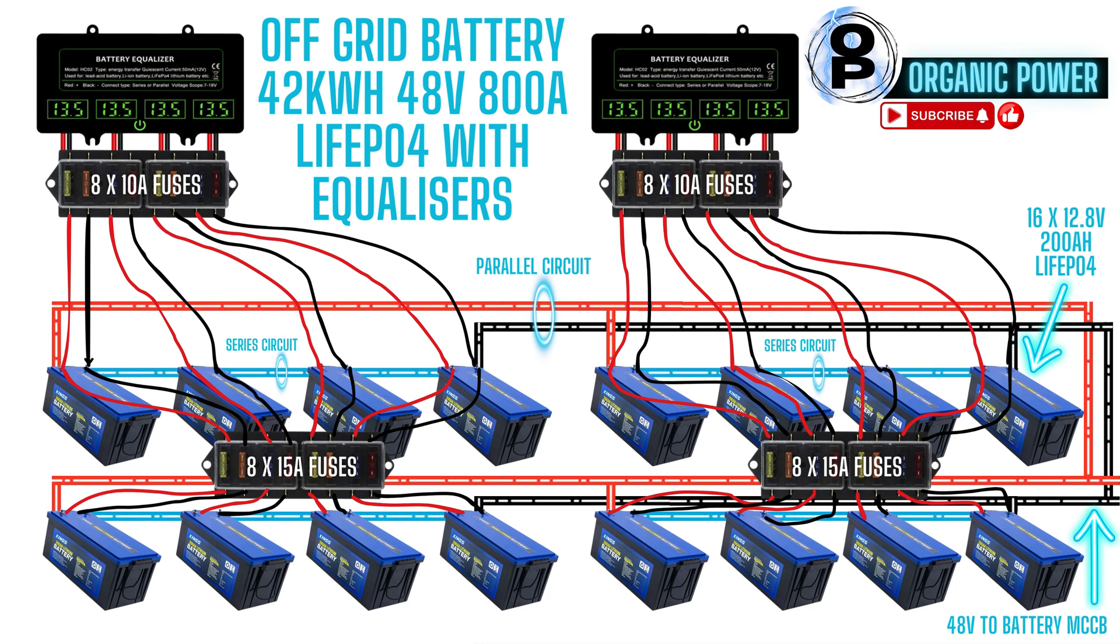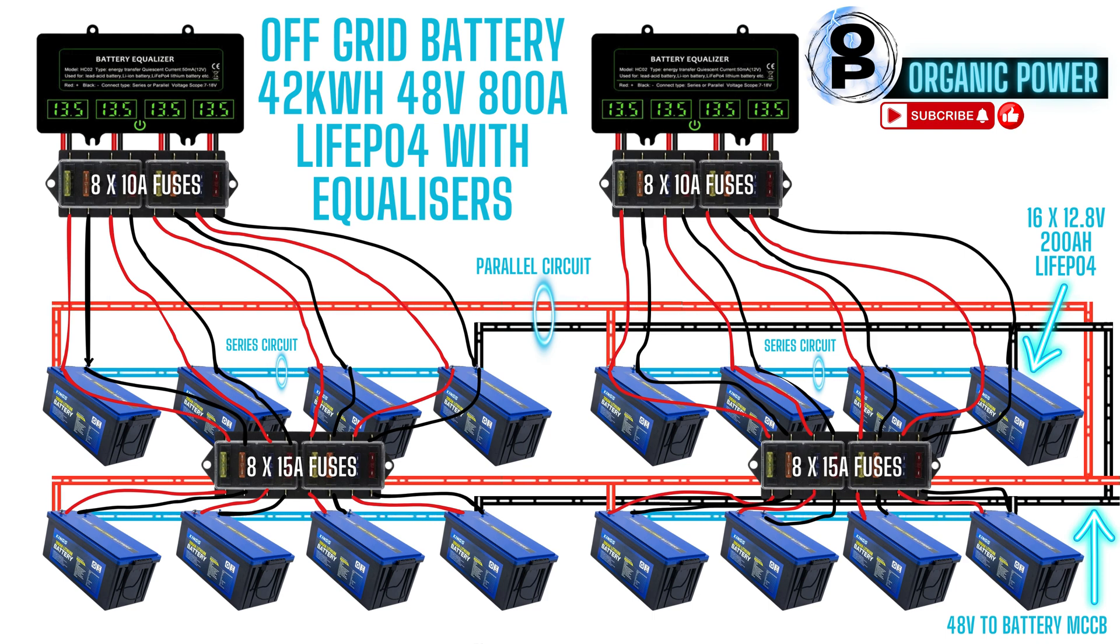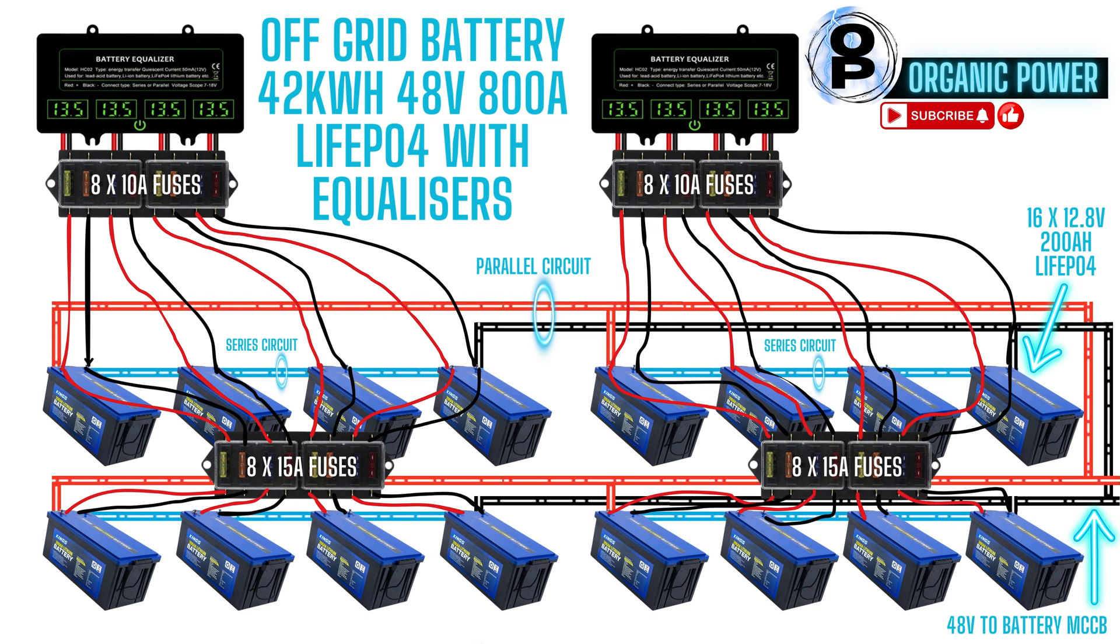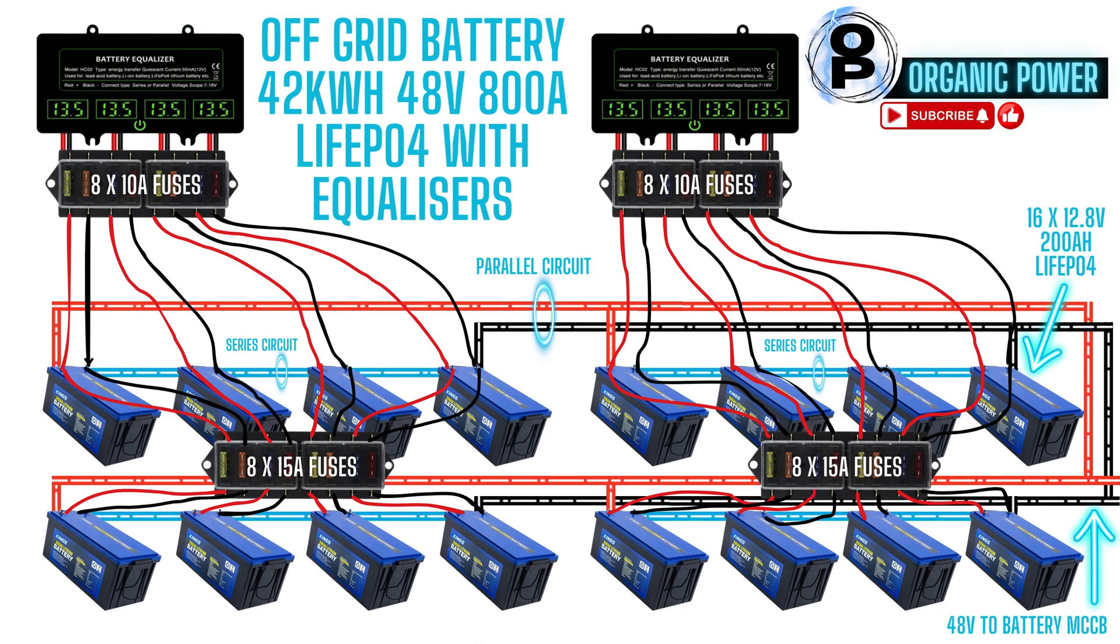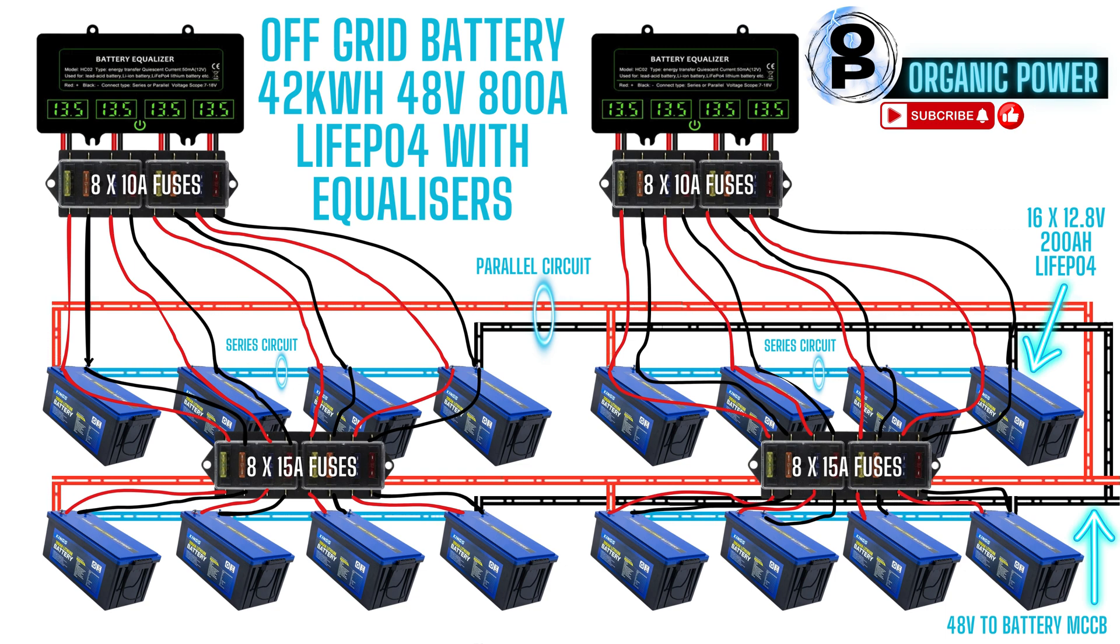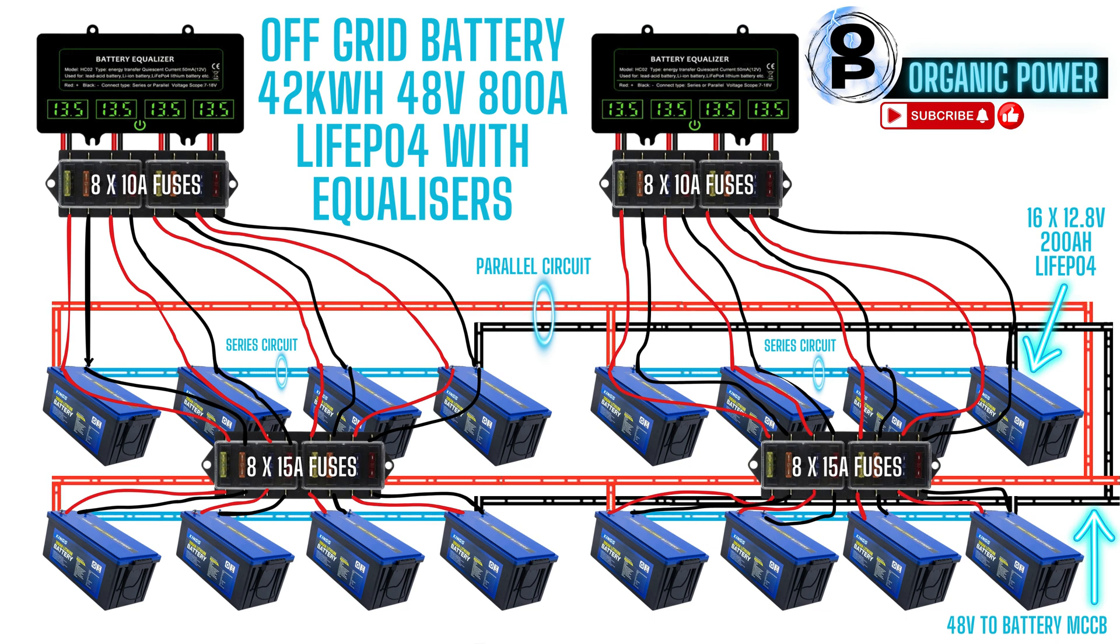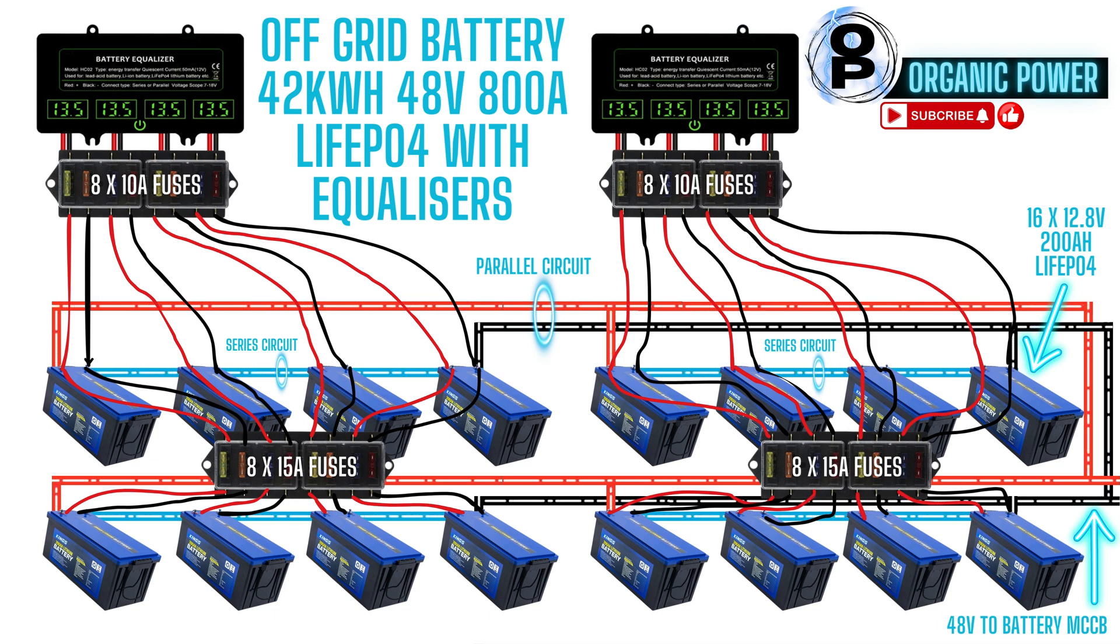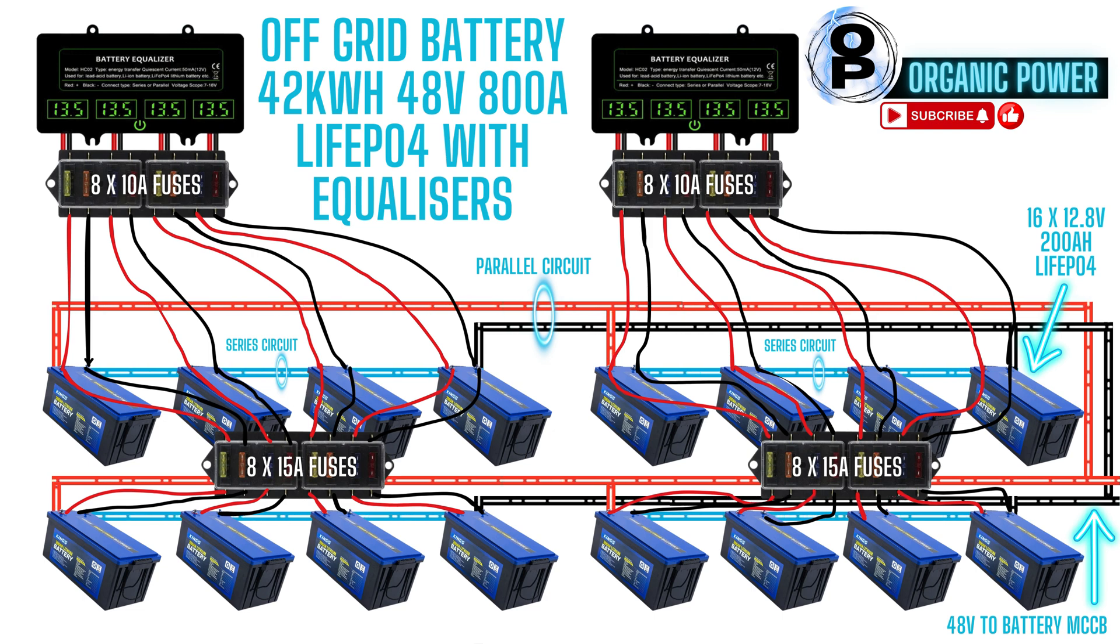To make sure the batteries are kept at the same voltage and the system remains safe, I have a battery equaliser. There is one battery equaliser per eight batteries. These equalisers can have one battery in parallel with another one on each of the leads into the unit. The battery equaliser circuit runs from the unit down into a fuse block. That fuse block has a 10 amp fuse protecting each of the cables down to the first bank of batteries.